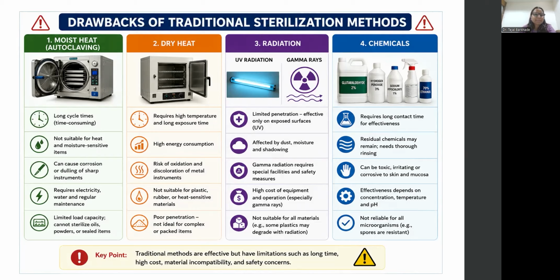Now we have dry heat. It also requires high temperature. Dry heat generally requires very high temperature and long exposure time, high energy consumption, and there is a risk of oxidation and discoloration of metal instruments. There are chances of that, and it is not suitable for plastic, rubber, or heat sensitive material again. So here also we have a limitation to sterilize heat sensitive material because we are using high temperature here. Then poor penetration, not ideal for complex or packed items. Yes, because again we are using high temperature here.